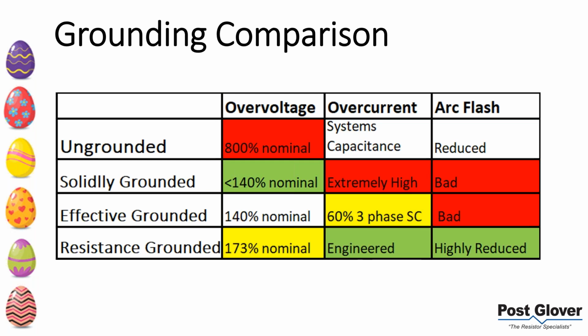You typically don't have a lot of current there because your impedance is high. You don't have a purposeful ground. It's air and insulation, so it's going to be low current there typically. Arc flash is typically reduced. Now I will say, if you get a system failure because you have the overvoltage condition, all bets are off. But in terms of a ground fault, your first ground fault, at least you're not seeing that as much.